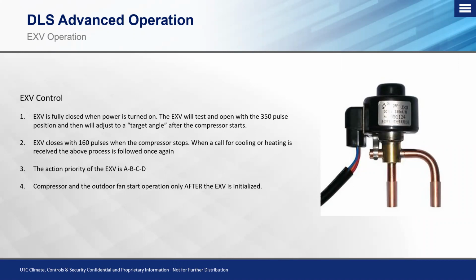Okay. So when a call for cooling or a call for heating is received, the above process is followed once again. So if you get a call for heat or call for cooling, the EXV is going to go up and it's going to modulate to whatever target angle based off of the T2B or the outlet sensor of that EXV. Essentially, it's acting like a traditional TXV with an outlet sensor on the evaporator. Except now, because the EXV is at the outdoor unit, we're taking the temperature on the outlet of the EXV. And now we're going to maintain our position based off of that temperature.